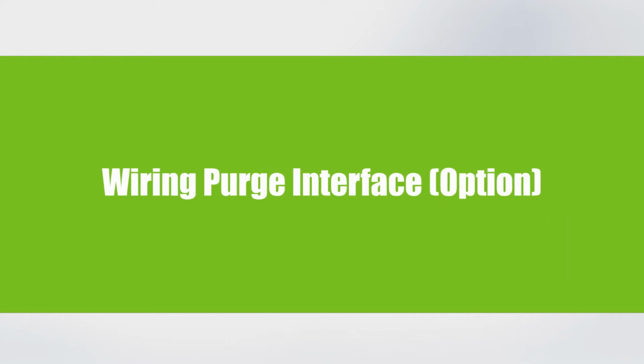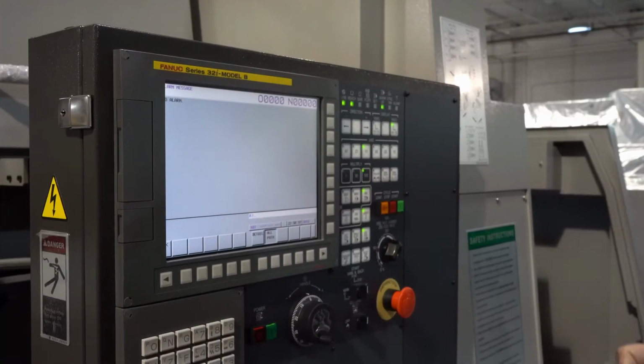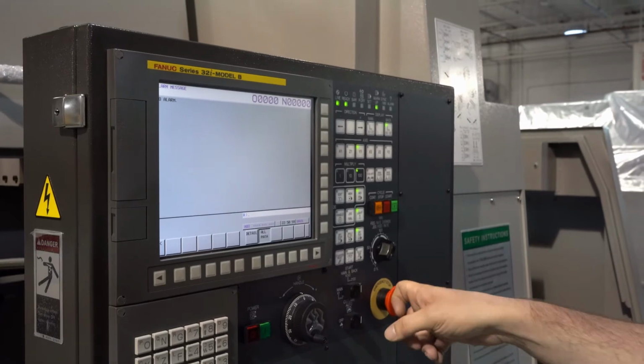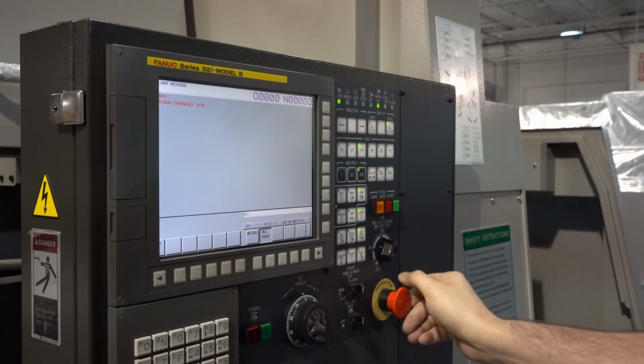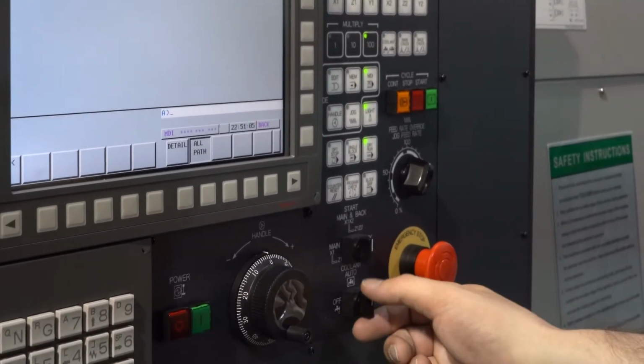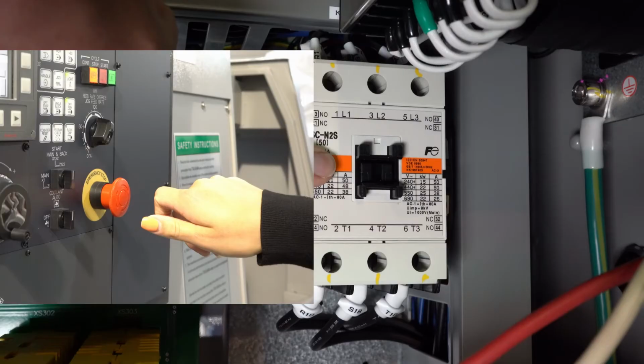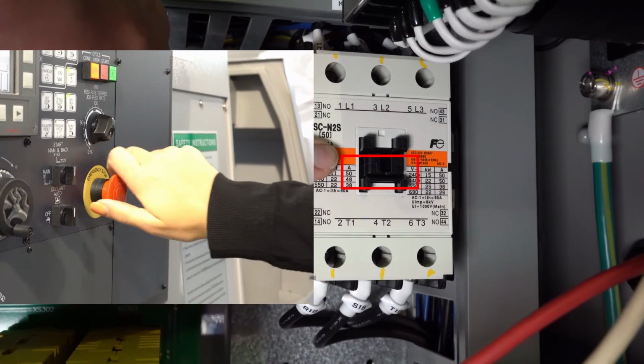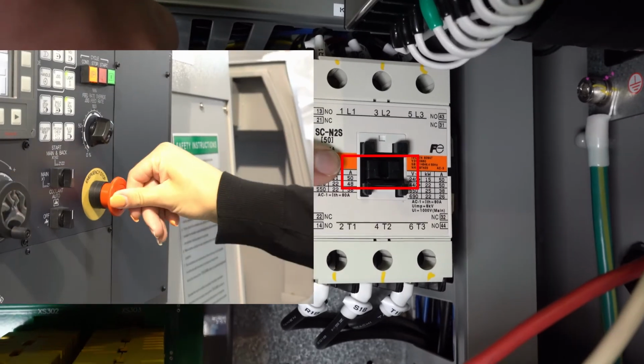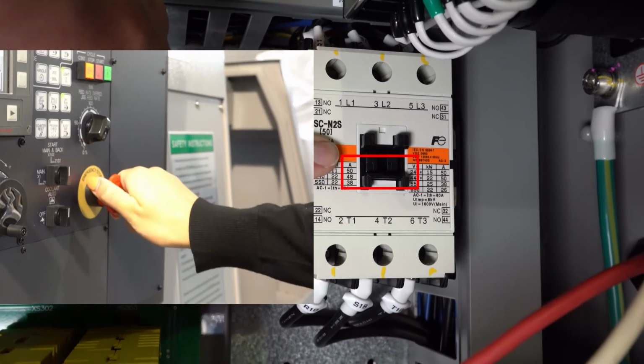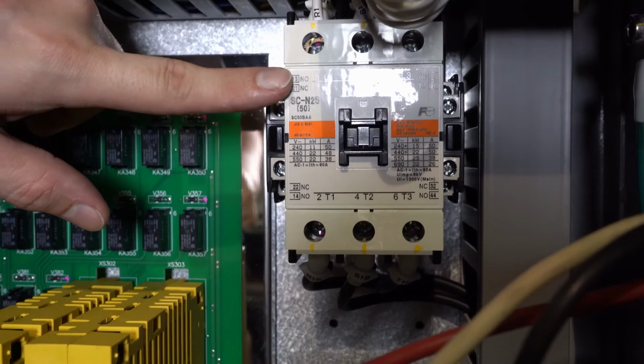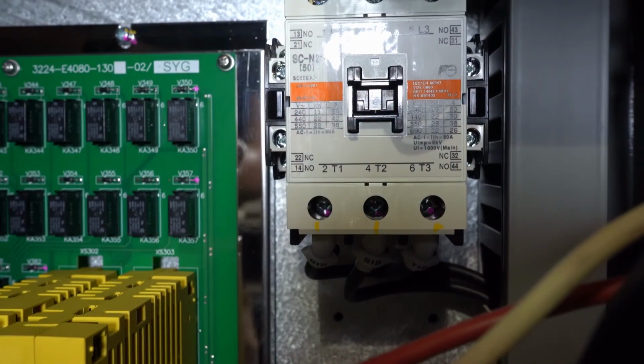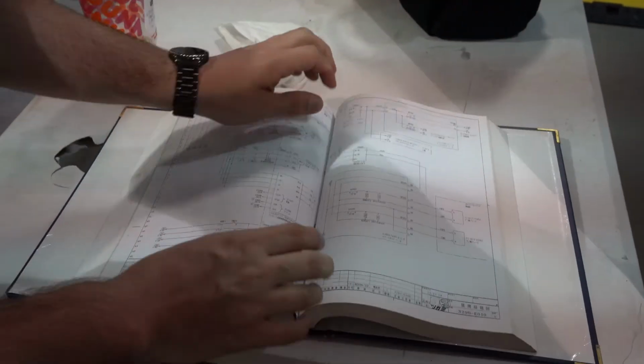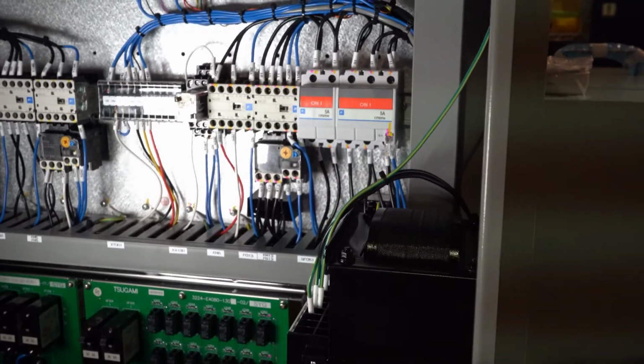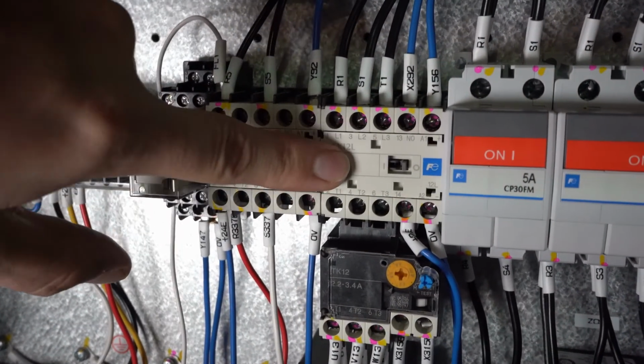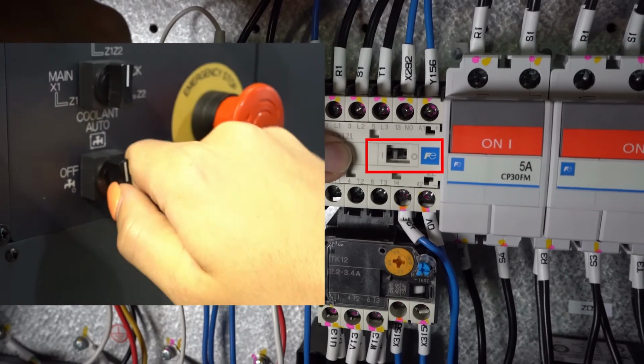Optional purge interface wiring. To install the purge interface, you'll need to be able to put the machine in and out of the ready and not ready states, and also turn the coolant on and off. Having a machine operator help you, cycle the machine between ready and not ready, and locate the contactor that goes in and out. This is usually referred to as the master control relay. This can also be found in the electrical schematic book with the machine. You'll also need to locate the coolant contactor, which can be found by cycling the coolant or finding the coolant pump in the schematics.